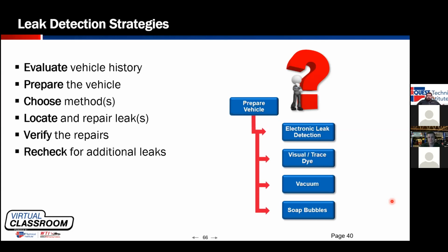If I know that, say, this car just had an engine replacement, I might be heading down and looking at the compressor manifold, things like that. Prepare the vehicle. So if I'm going to do electronic detection, I need to make sure that that system has refrigerant in it. If there's no refrigerant in the system, there's nothing for my leak detector to pick up. Same thing if I want to use dye, I need to make sure that that system has dye in it. If I'm going to try to do vacuum decay leak testing, possibly listening for a vacuum leak with an ultrasonic detector or something like that, I need to recover the refrigerant from the system and then pull that system into a vacuum. If I'm going to do soap bubbles, I need to, again, make sure there's something in the system to bubble.